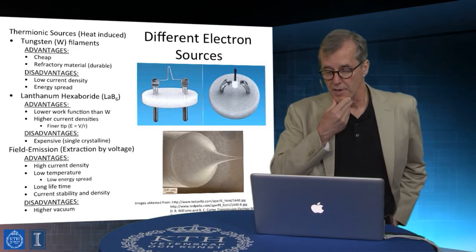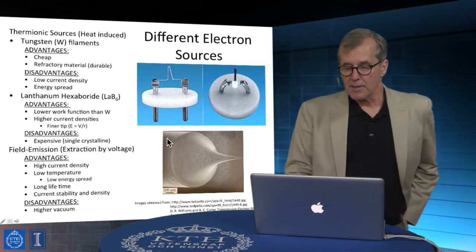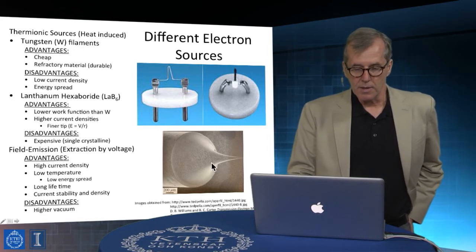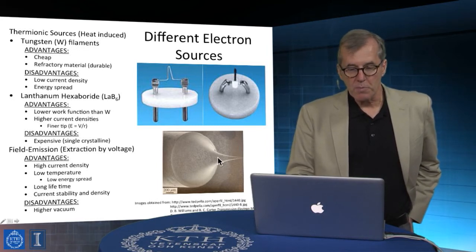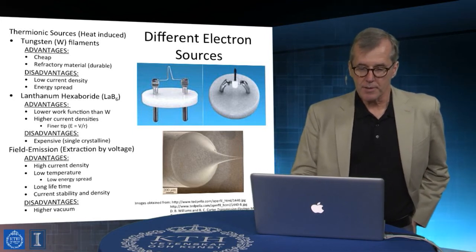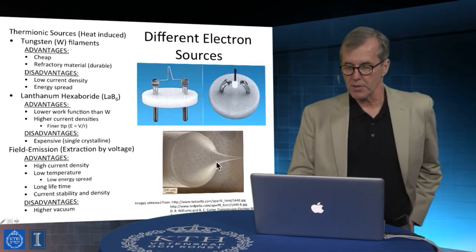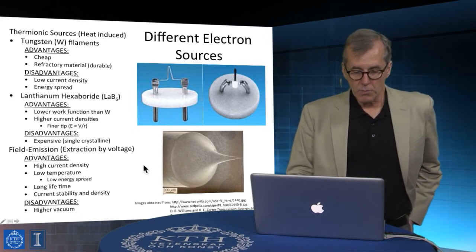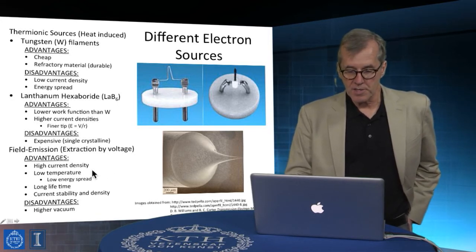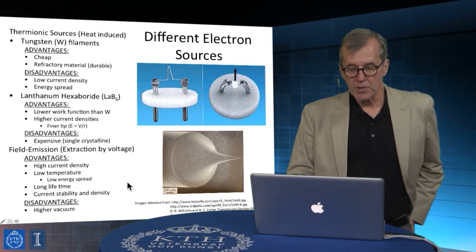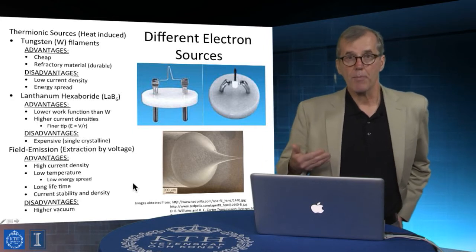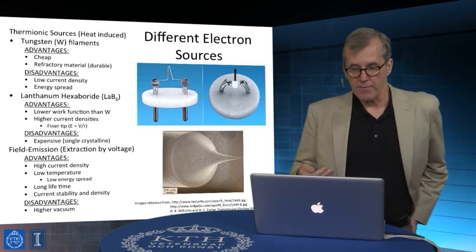So, electron sources for these kinds of instruments. At the limit of atomic resolution, you're going to have to really be working with a microscope that has a field emission source, and those are really quite powerful electron sources that deliver high current densities, and actually they're reasonably robust, but rigorously require that the column operate at ultra high vacuum conditions.